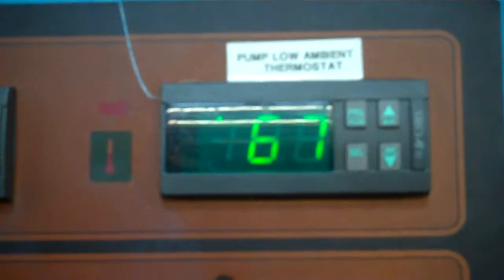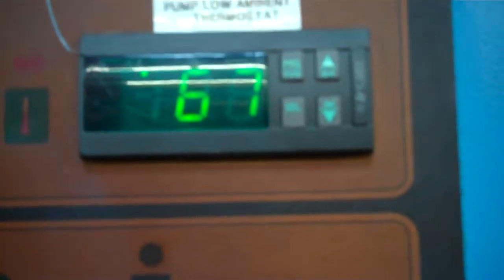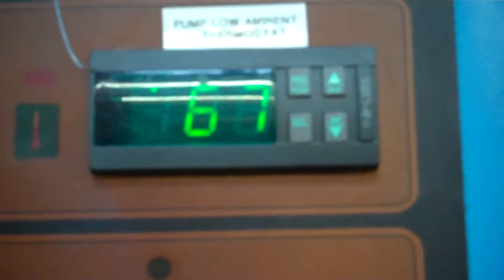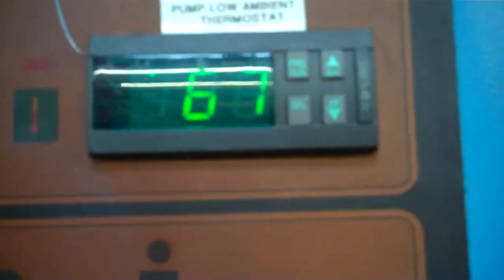This temperature controller on the right here, that's our pump low ambient thermostat. That's simply if this were going in either an outdoor installation or a cold installation. It's going to be installed indoors for this customer. But what that does, if it got too low of a temp in the ambient temperature, it would make sure the pump is on all the time no matter what, so no freezing occurs.